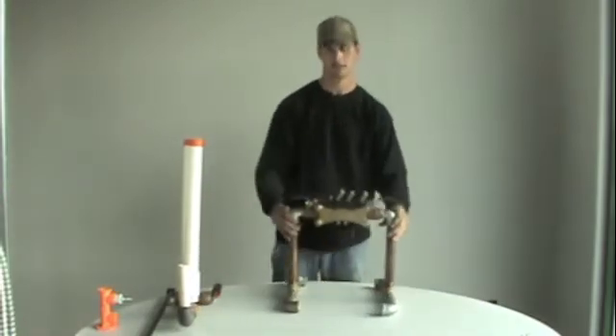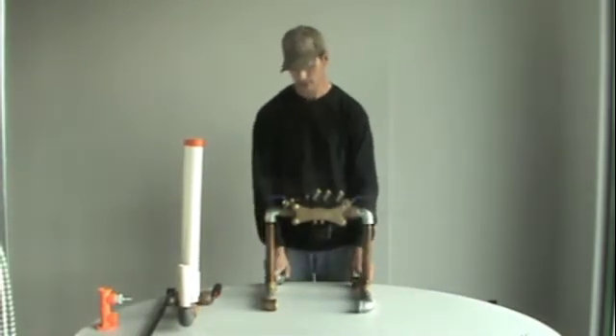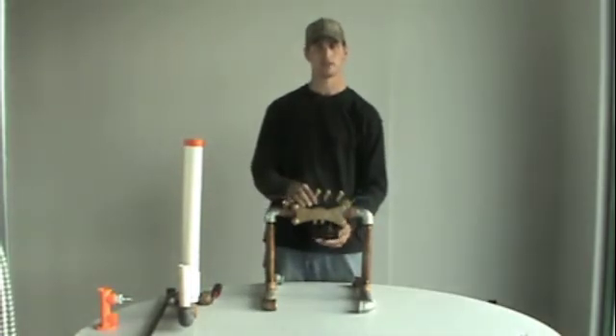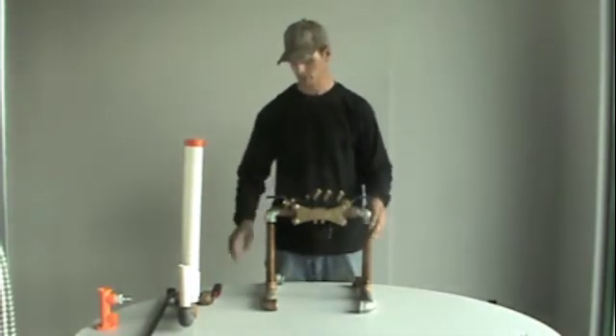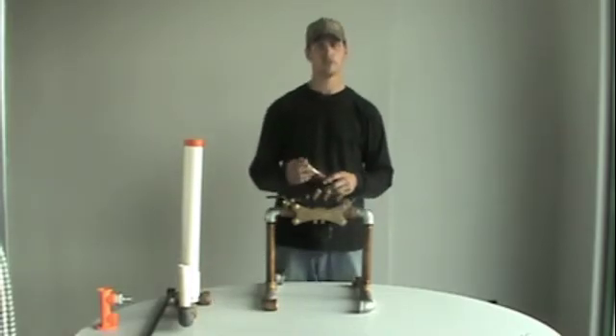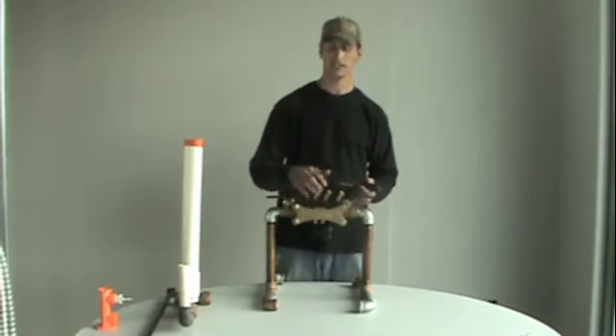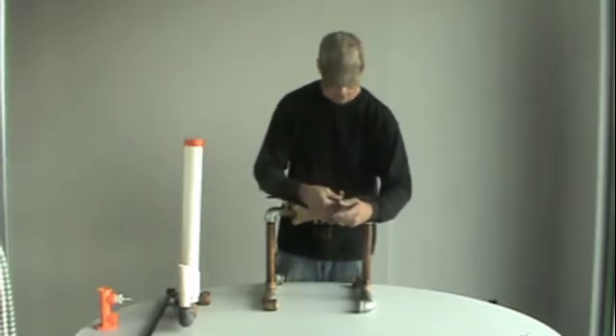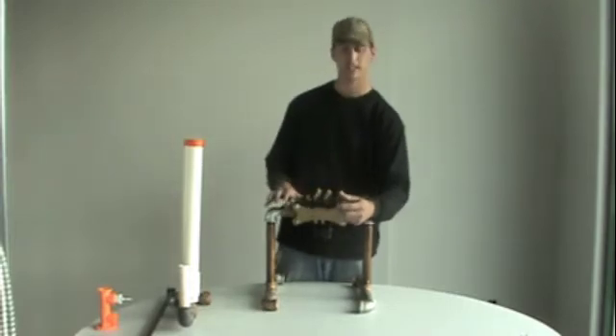And then, what we'd like to do is essentially take out the vessel of the Wilkins backflow. There's a few steps that I'd like to show you. First, we would like to open these three test cocks. This will actually reduce the pressure from the irrigation line. These are ball valves.